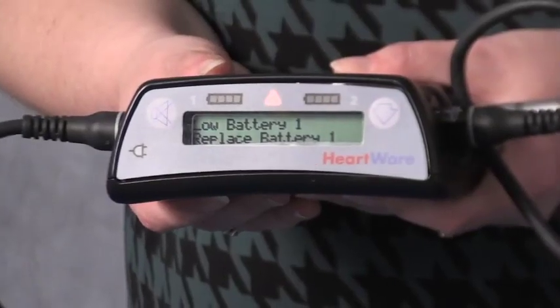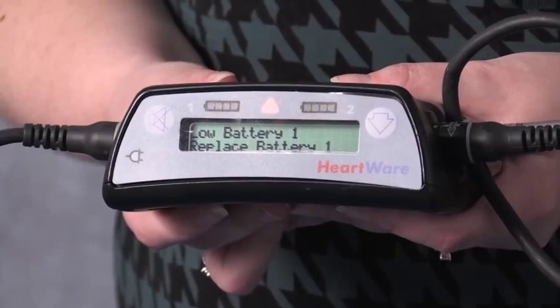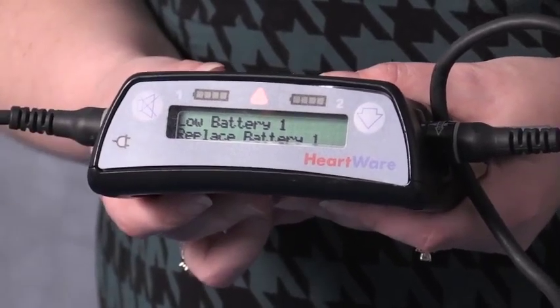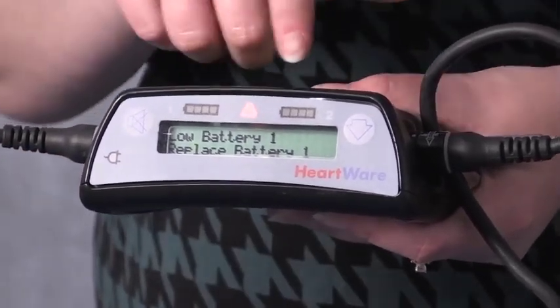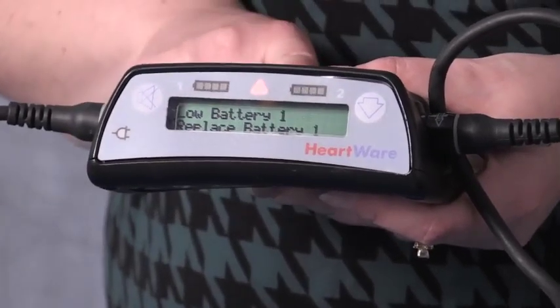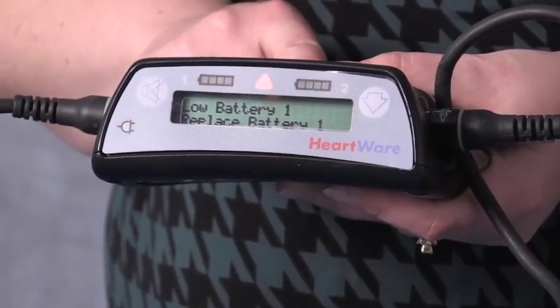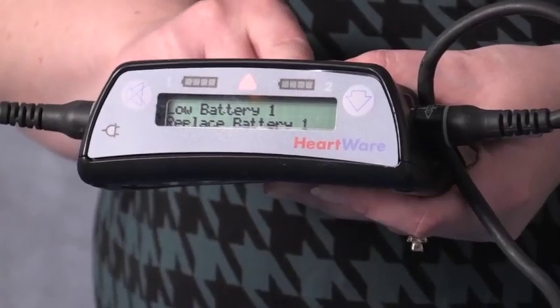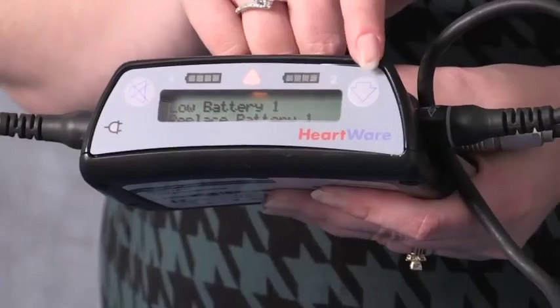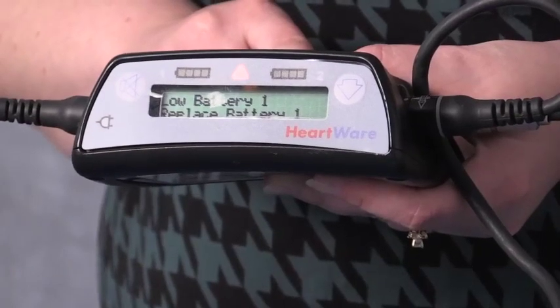This is our HVAD controller. It's very similar to the HeartMate 2 controller, but a little different in some ways. We still have an alarm silence button, and we have battery indicators at the top here—as you can see, this controller is alarming because one of my batteries is low. Our alarm indicator, the triangle in the center, will turn yellow, orange, or red depending on the status of the alarm. This is the toggle button, and our arrow toggle button allows us to scroll between the various menus.